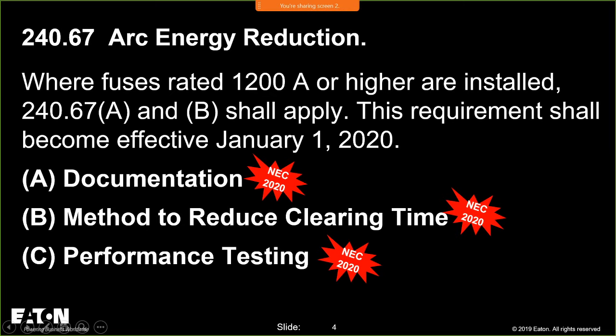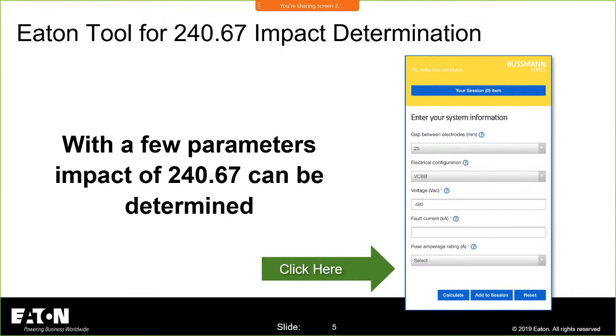I don't believe, let me just check my book. Just make sure that my book is right. But 240.67 doesn't say A, B, and C. No, it says A and B shall apply. I believe that should be C too. But in any case, it still has the January 1st date. So we released the 2020 code with an effective date of January 1st, 2020. So we have a little bit of cleanup to do on this requirement, but we have it separated into A, B, and C: documentation, method to reduce clearing time, and performance testing. You'll notice there were changes in all three of these. So these still get the chance to be modified over time.